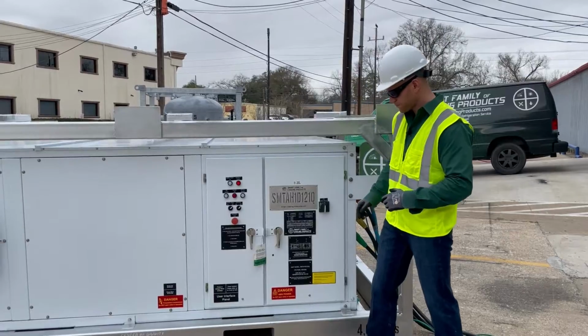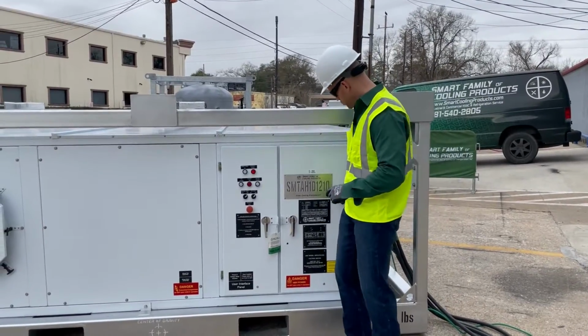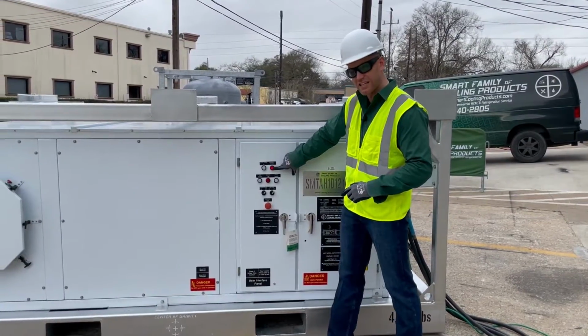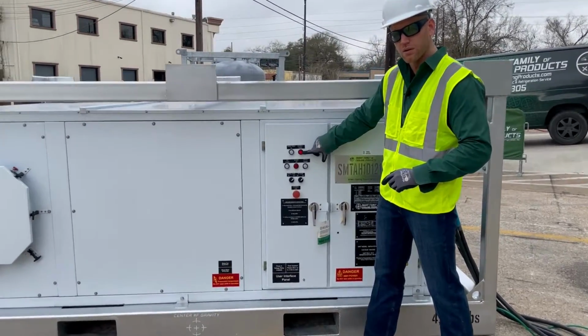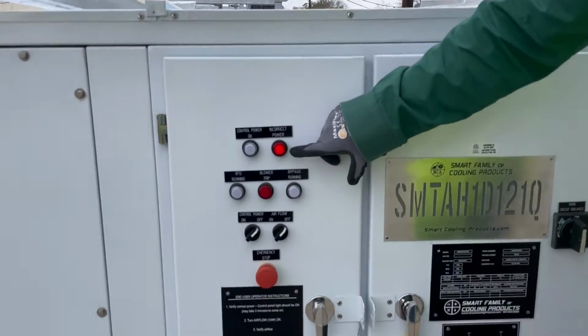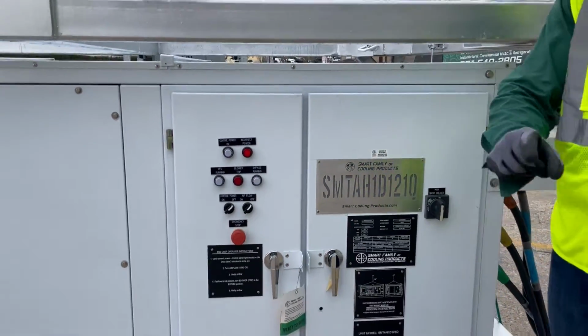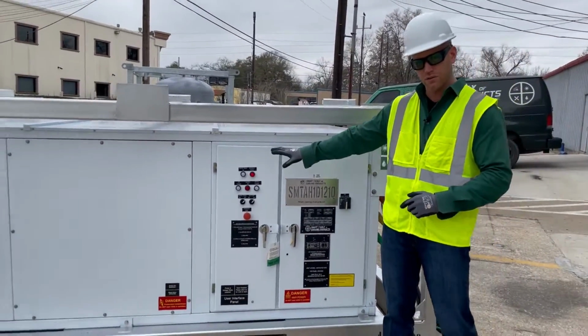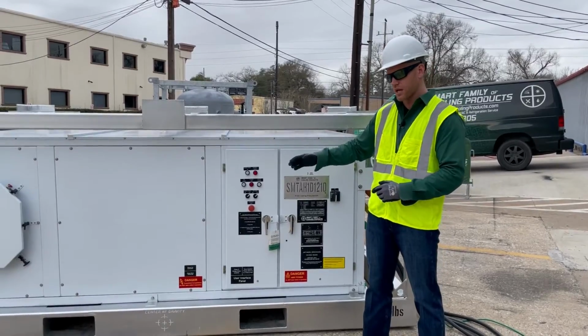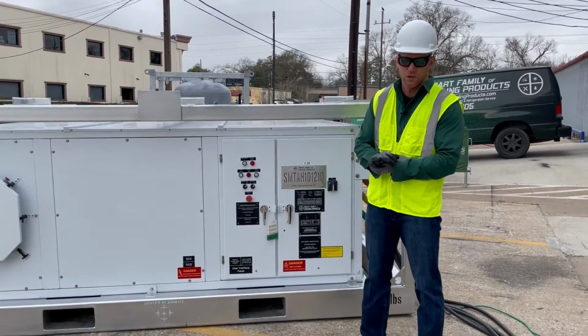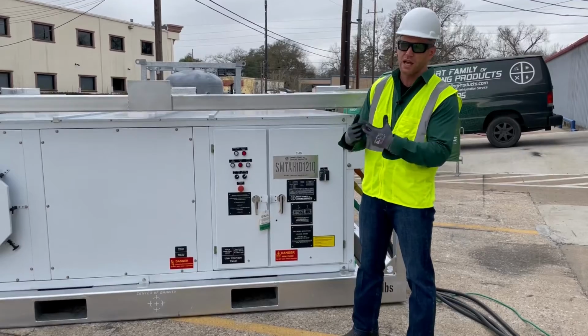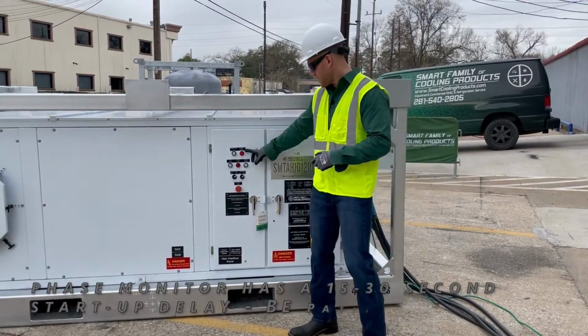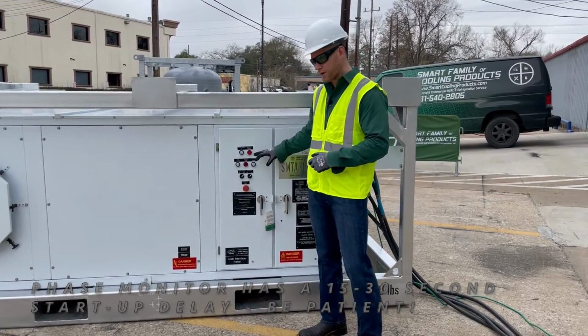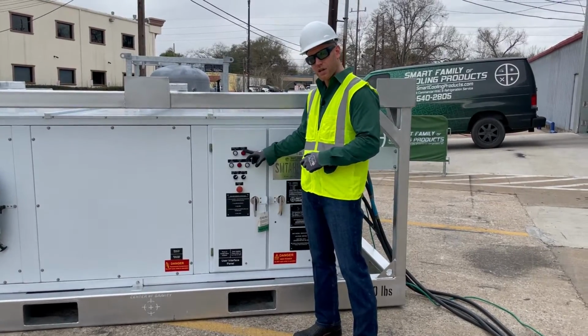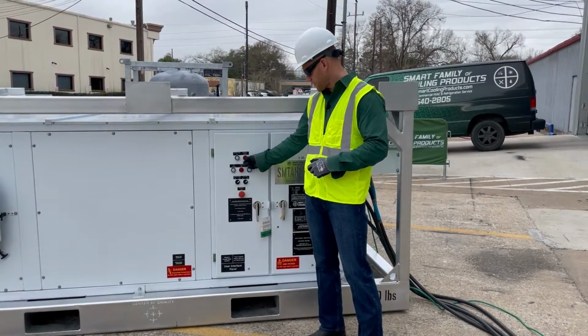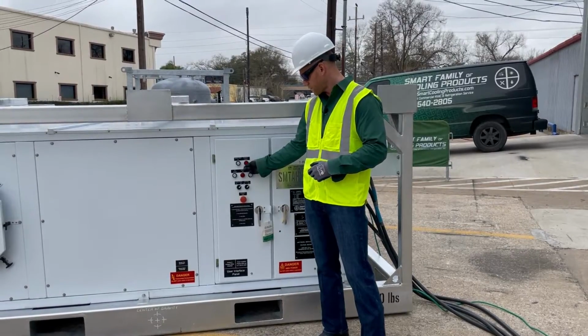the on position. As soon as you grant this unit power, you will notice that the incorrect power light comes on. That's normal, that's standard. The reason for that is we have a phase monitor on this particular machine that's relatively sophisticated, and it has a startup delay. So we don't want to immediately run motors on any rental gear. So what that means is we have a time delay on our phase monitor that does not grant us power until that timer has gone off. You'll see the timer's gone off and the incorrect power light is off. Okay?